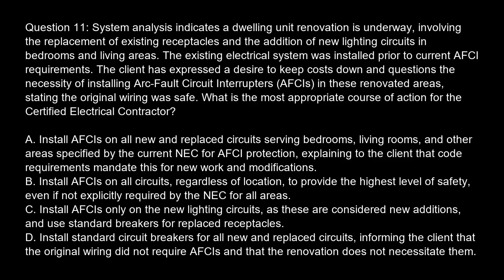Option A. Install AFCI on all new and replaced circuits serving bedrooms, living rooms, and other areas specified by the current NEC for AFCI protection, explaining to the client that code requirements mandate this for new work and modifications. Option B. Install AFCI on all circuits, regardless of location, to provide the highest level of safety, even if not explicitly required by the NEC for all areas.